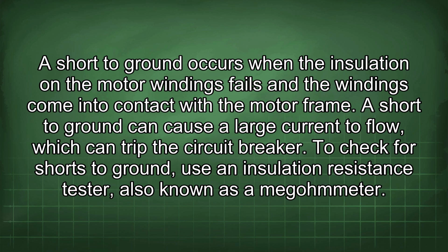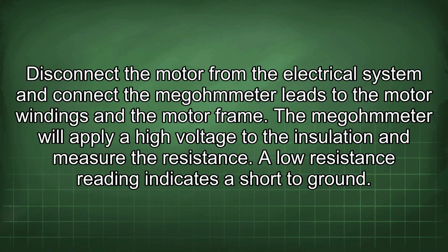To check for shorts to ground, use an insulation resistance tester, also known as a megohmmeter. Disconnect the motor from the electrical system and connect the megohmmeter leads to the motor windings and the motor frame. The megohmmeter will apply a high voltage to the insulation and measure the resistance. A low resistance reading indicates a short to ground.